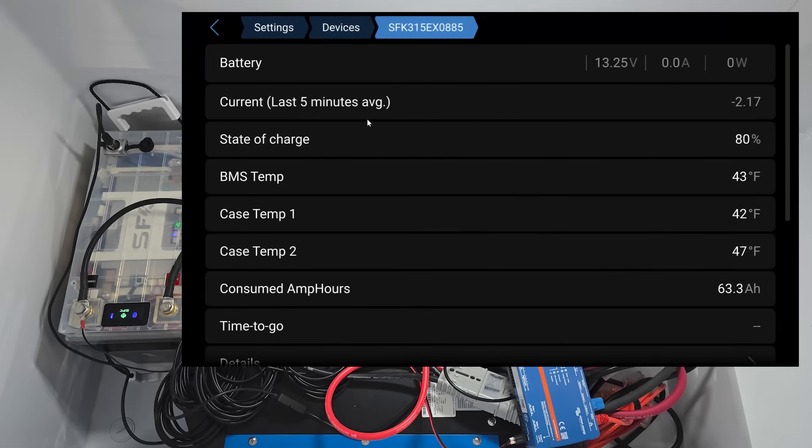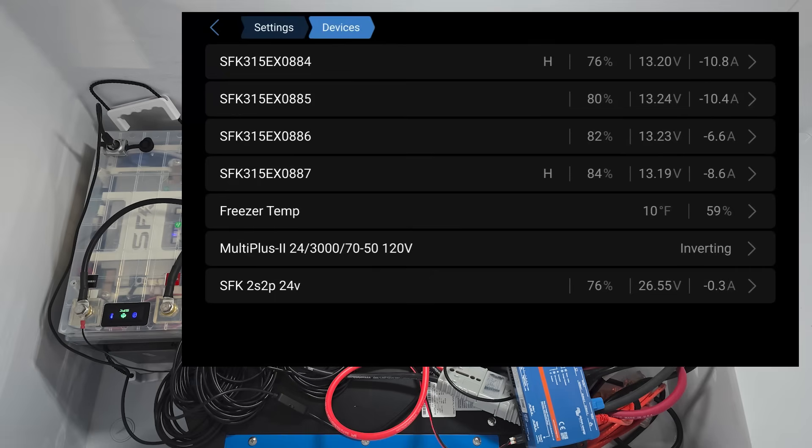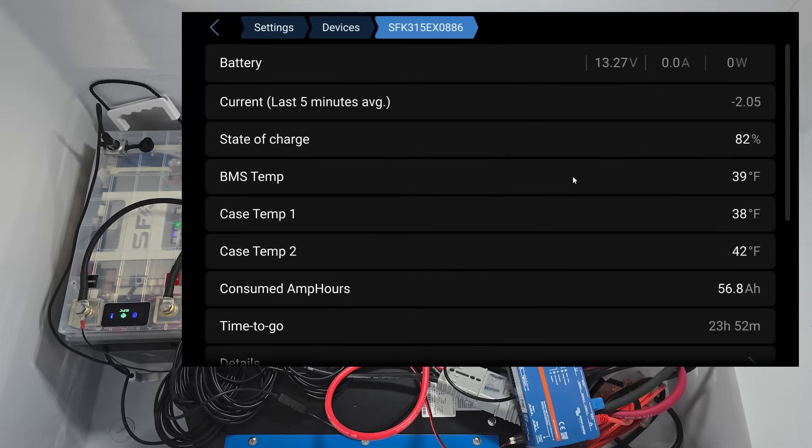So if we look at another one, this is, like I said, this is 85. And oh, look at that H. You see that H that's an indication when the heaters are turned on. So that's what the synchronized heating is doing. It's turning on heating for all of the batteries simultaneously. And it's going to try to keep them within that 41 to 55 range, or whatever you set up on. And when it runs, it runs it to where it's pulling and then it'll run for a little bit. Stop. If it hits the right temperature, then it'll stop. Now, as you can see in this one, 38 case case, one's a little lower 38, 42. So it's probably going to run again when it does its pulling again.